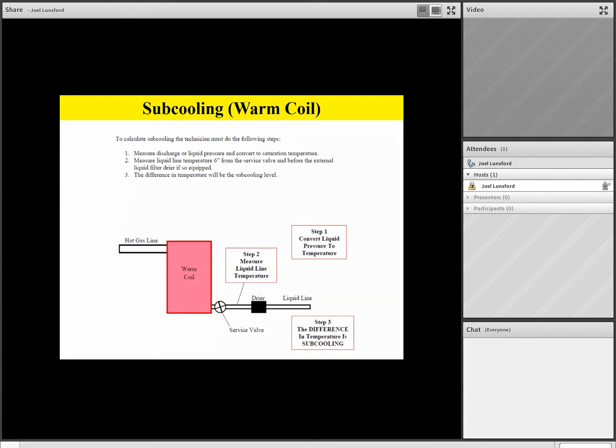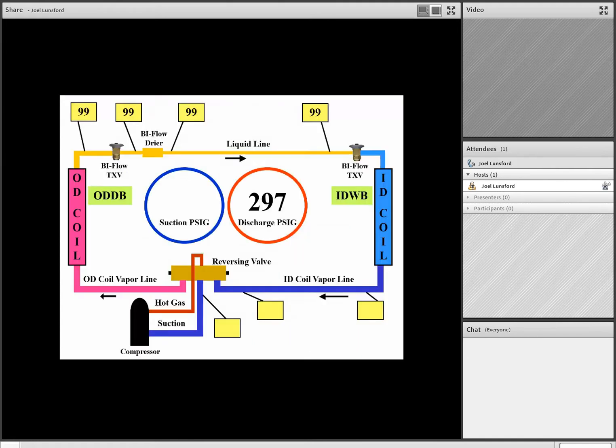So in our example here on the R22 screen, we see that we're looking at the high side pressure now, or the discharge pressure. So in our example, we have 297 pounds of pressure on the discharge gauge that we're looking at on this particular service call, or this example. Now, team, you'll notice that there's a white background on the gauges. Excuse me, that means this is an R22 service call. In addition, you'll also notice that we've deactivated the temperature blocks on the suction line or the vapor line, and we have activated the ones on the liquid line.